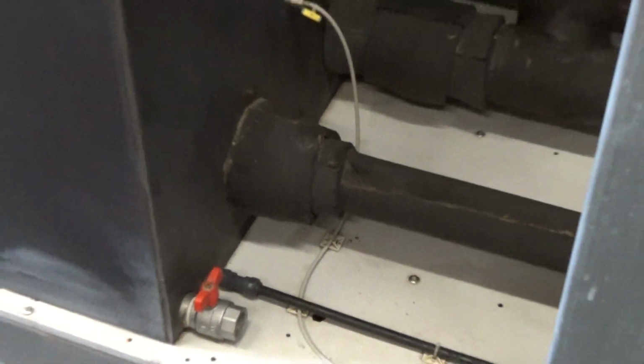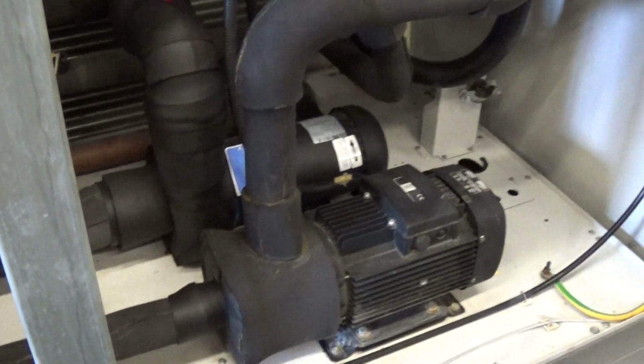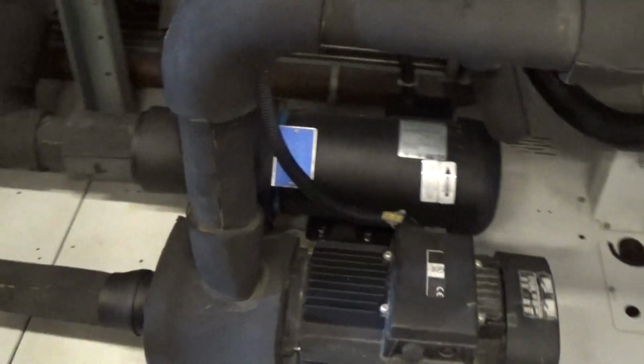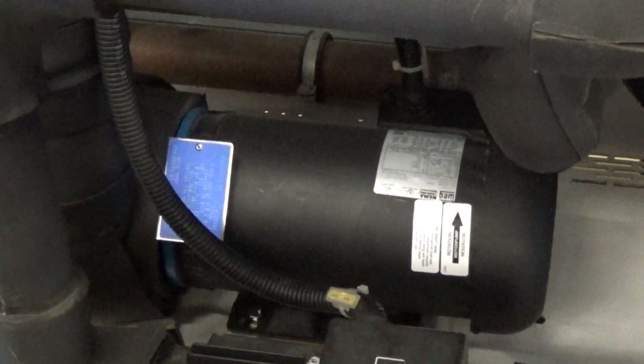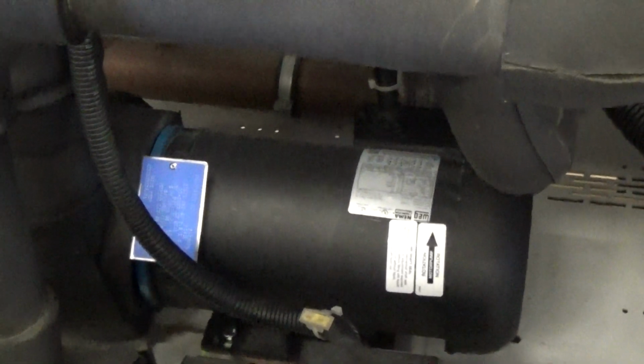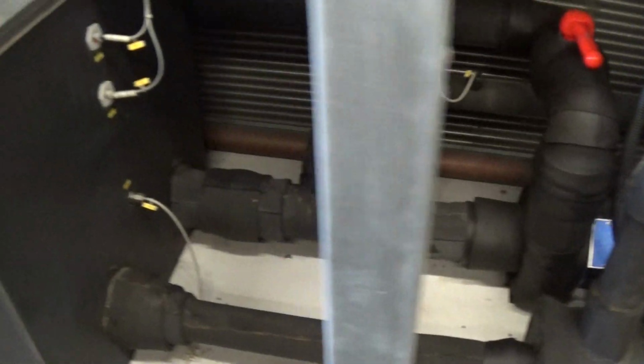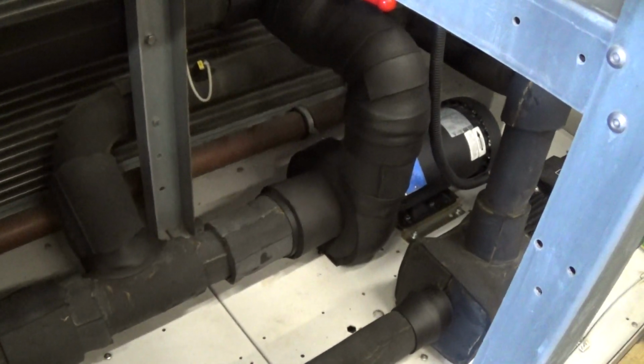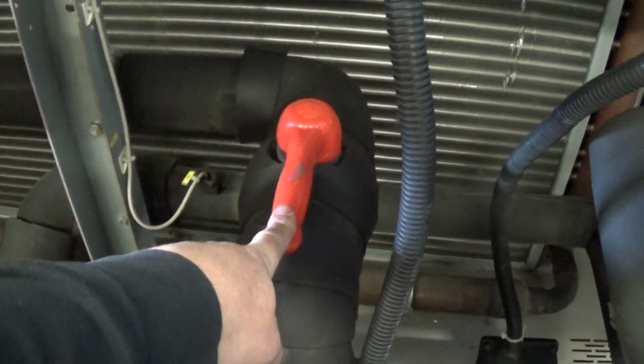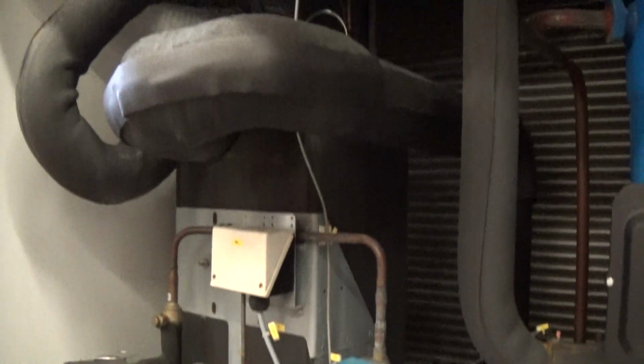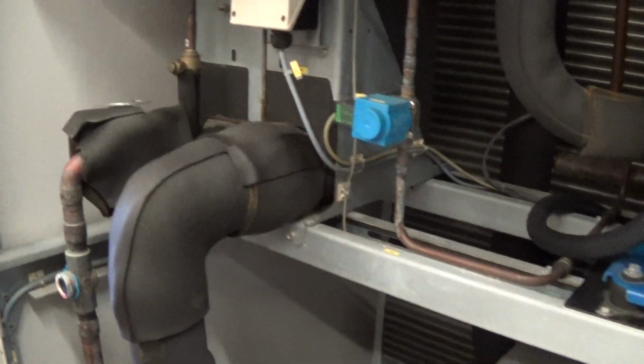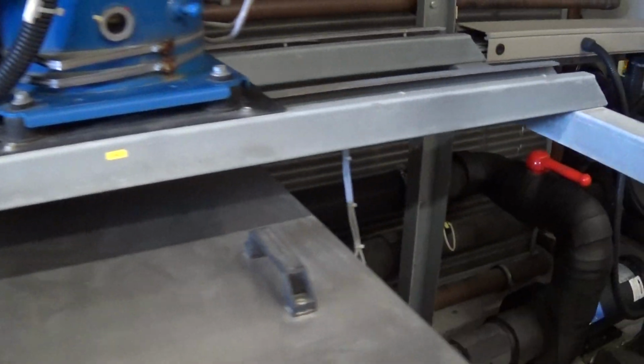Has a drain here. This is a nice system in that it's a 2-pump system. In fact, the primary pump, or the chiller loop pump, is a brand new pump we did just install. So what does a 2-pump system mean? It means that the chiller loop pump, which is this new one, suctions or draws from the tank, and it comes up here. The discharge, and this valve we can leave open, outputs directly. It goes behind the tank to the brazed plate heat exchanger or evaporator that's right there. Then discharges back into the tank.